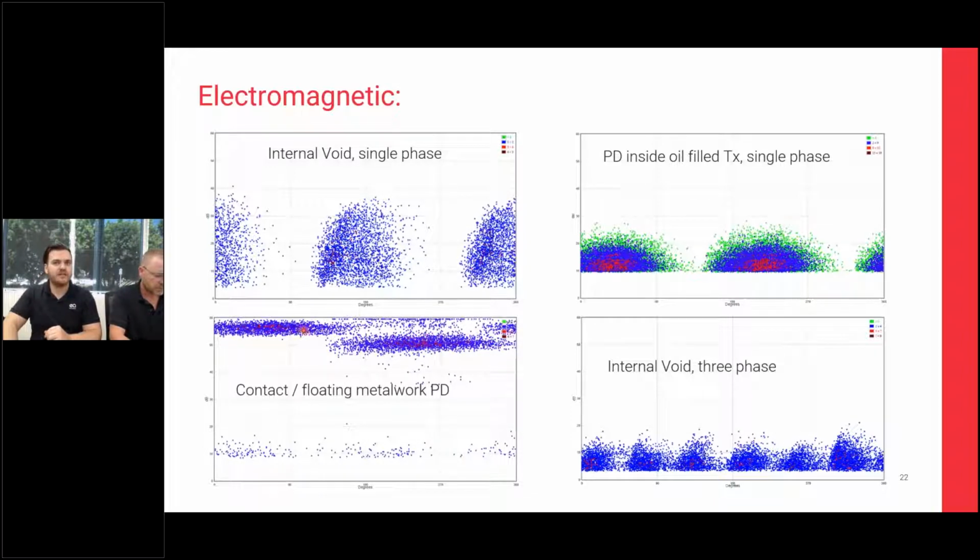They are still 180-degree separated clusters, but they are long, flat bars of activity. And these type of signals you'll see a lot more in the outdoor yards than anywhere else, and it's very identifiable. The third type, and I think we just got a question about this as well, is what will it look like when you have multiple phases of activity involved?